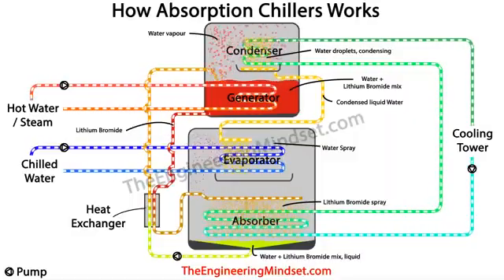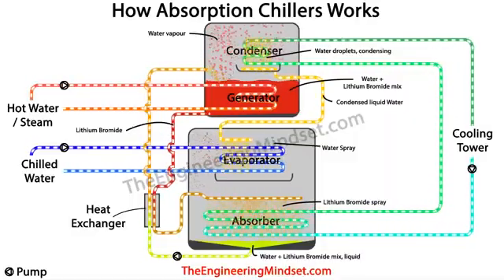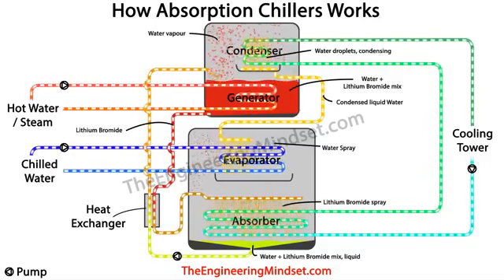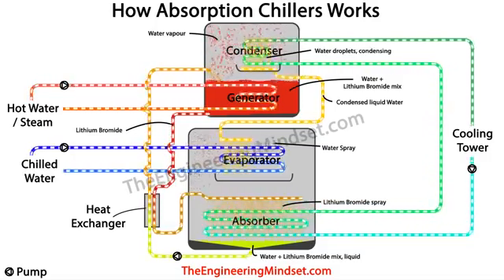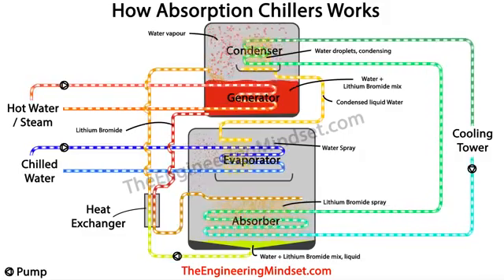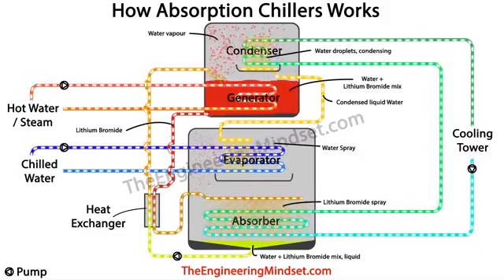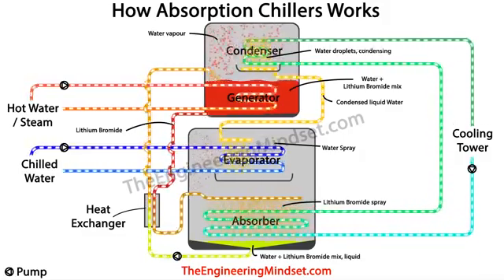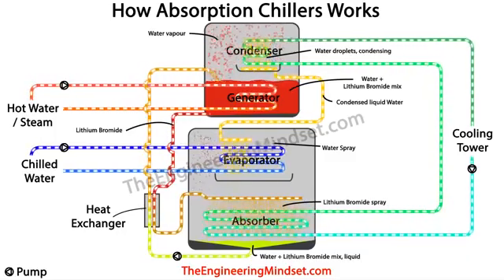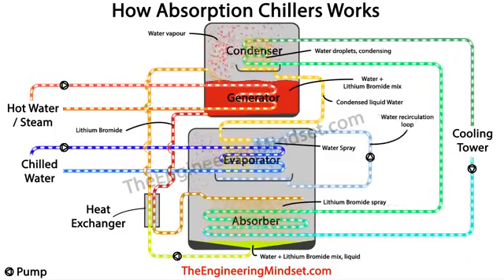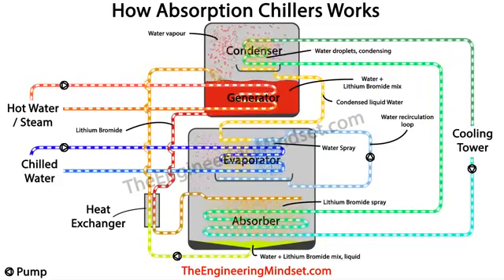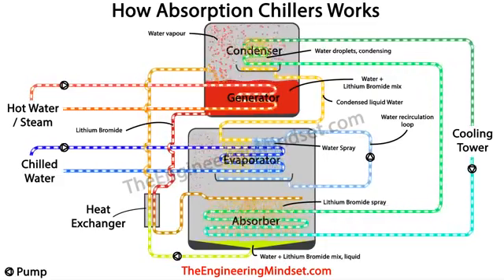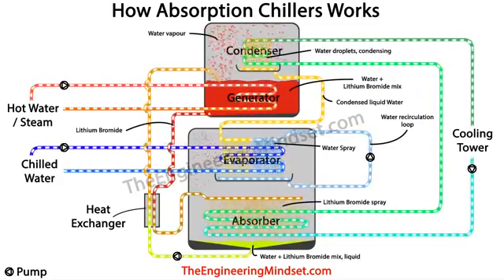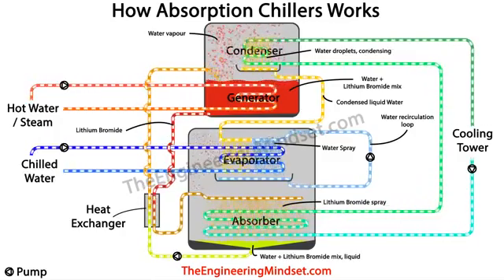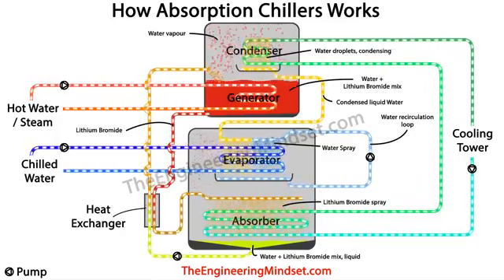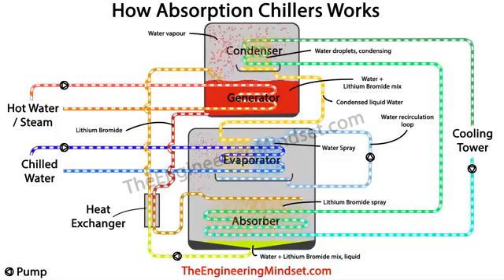So the chilled water circuit has now given up all the unwanted heat, and by the time it leaves the chiller it should be around 7 degrees Celsius, which is approximately 45 degrees Fahrenheit, and this water is now ready to be pumped around the building again to collect more heat and bring it back to the absorption chiller. Another loop will recirculate any water that missed the tubes and didn't boil off into steam or water vapor, and this will be pumped back to the top of the evaporator and sprayed again and again and again until all of it evaporates into steam.